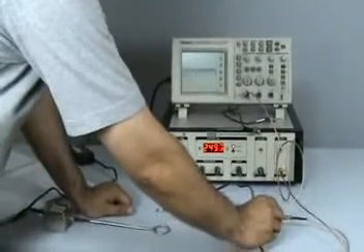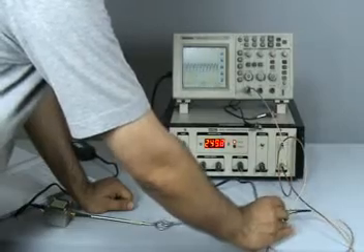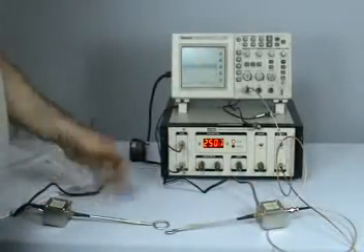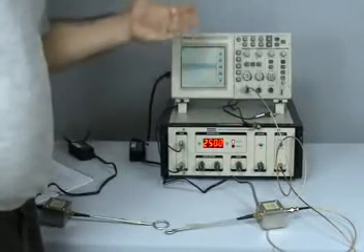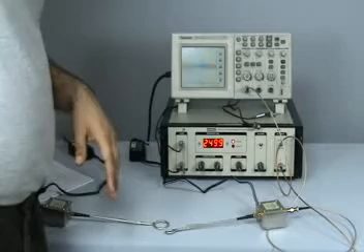We need to keep the level at the input of the preamplifier below 10 millivolts for best operation of the preamplifier. So we've seen that the preamplifier can be used to increase the sensitivity of a CRO. This has a very high bandwidth of about 3 gigahertz. So any CROs with 100 megahertz, 200 megahertz bandwidth, the sensitivity of the CRO can be increased, and its use be enhanced for EMI EMC applications.